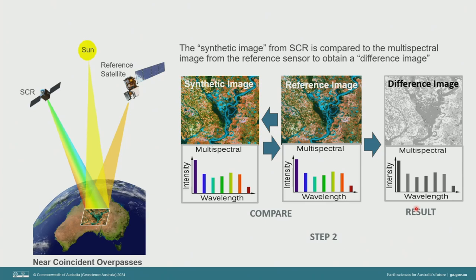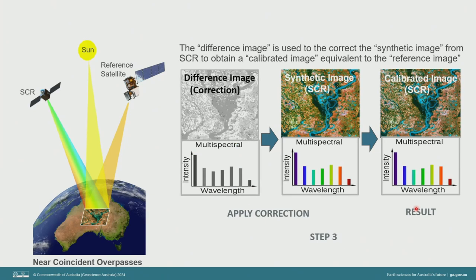You would then generate what is called a difference image from this exercise and use it to correct the SCR image, applying corrections because the reference is closer to the truth. We know it's monitored, and we know it's got a traceable reference to a known standard. The difference image is used to correct the SCR image, ending up with an image equivalent to the reference.